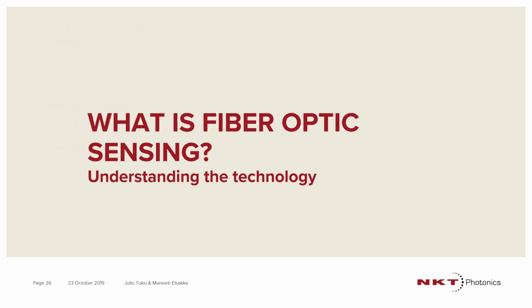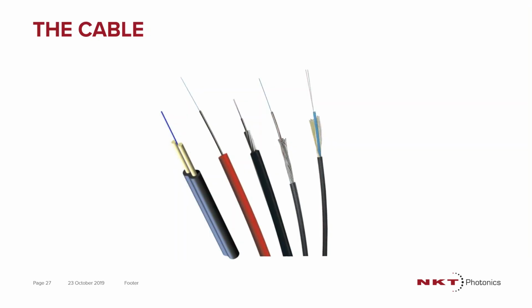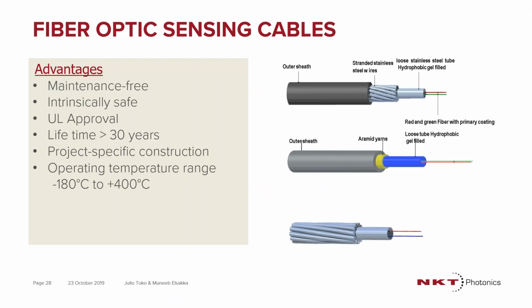Now, what is fiber optic sensing? I'm going to go a little bit more into the details of the technology. It's a technology that has really benefited the telecom industry, but we're also using it more in terms of sensing. So we will start with the cable. The fiber optic cable has to be UL approved or FM Global approved, or it has to be really following the standards with the controller. So it's a system together.